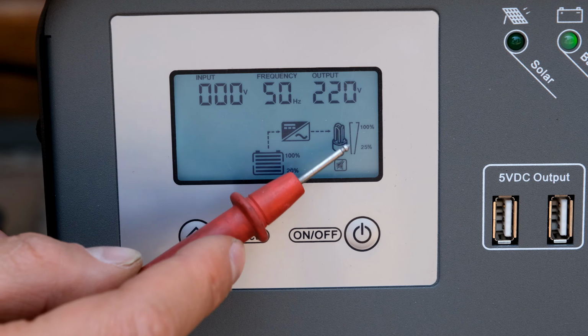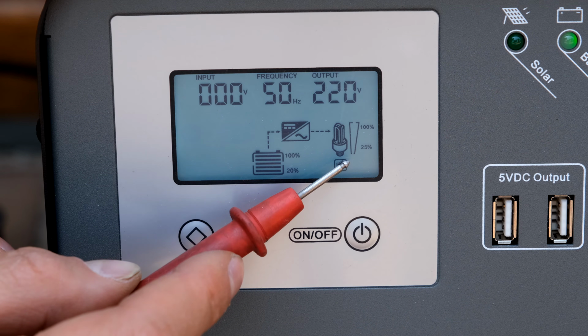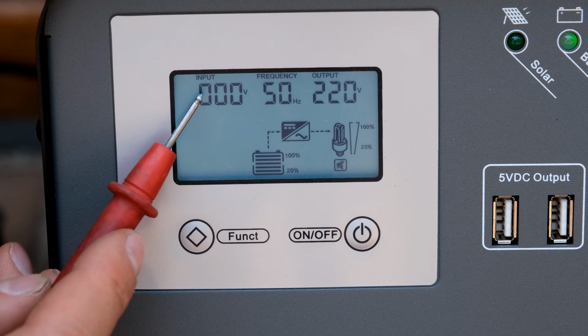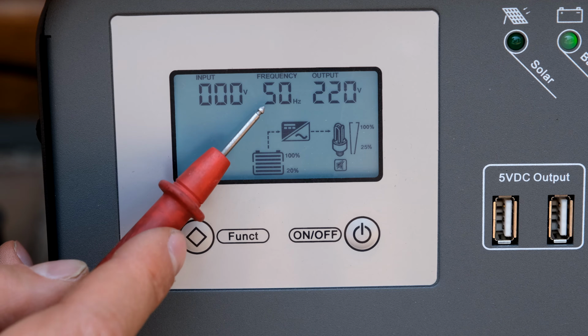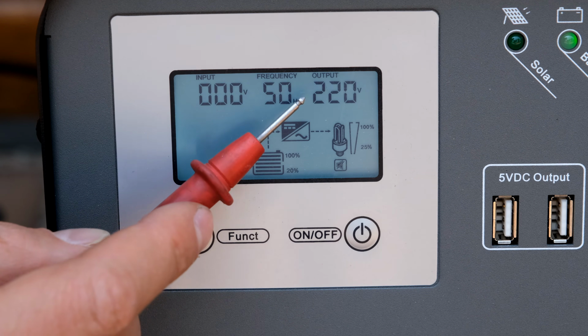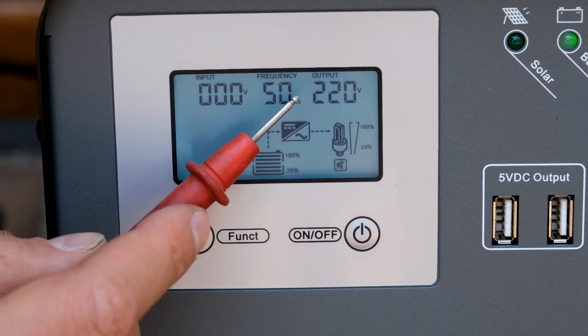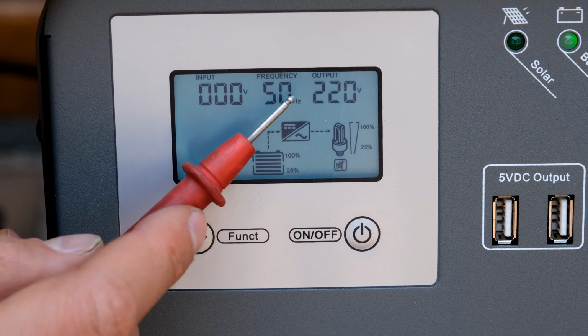The bar graph here on the side is very low, so it's showing me it's a very light load. The input is at 0 because I've unplugged the mains. The frequency is at 50, which it is - it's 49.8, close enough. And the voltage on the output says it's 220. My meter is saying 222, but also close enough.